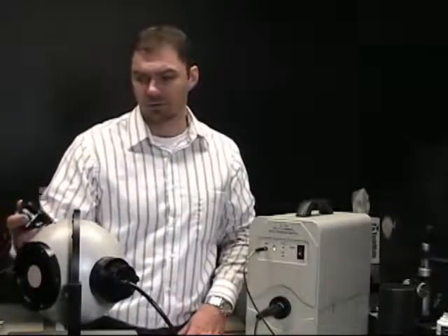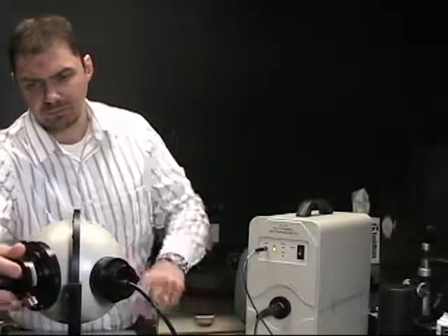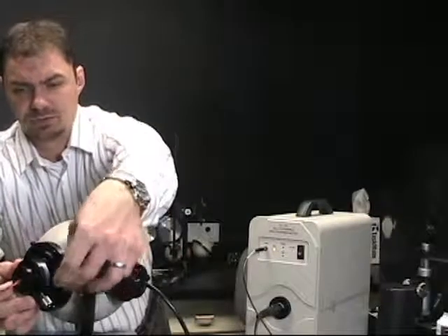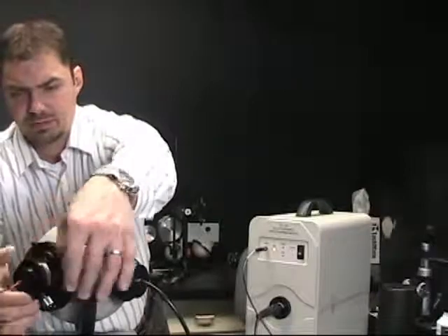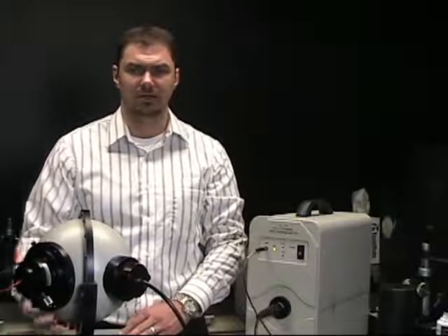This is actually the fiber we discussed yesterday that dealt with recalibrating the system for correcting for absorbance of your LED holders. So essentially, you would load your LED into the adapter, set the adapter onto your port, tighten down the three securing screws, hook up your power to your LED holder, and then move into the portion of the software entitled total luminous flux. You'd go through a calibration and a measurement, and I'll show you that right now.